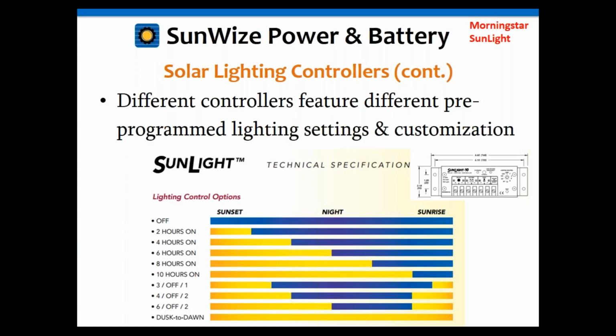And then you'll see for other units as you move up in complexity, the general programming structure is more or less the same. You have these dawn and dusk set points, and then you can basically control through custom programming the amount of time before and after each one of those events the lighting is triggered. So basically you could have it come on a certain amount of time before dusk even, and we'll get into that as the complexity goes on. But for some of these, you basically have a set number of presets from the factory, you select which one you want, and then it should work automatically.